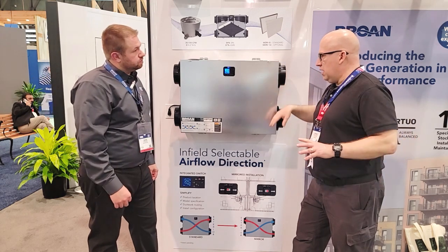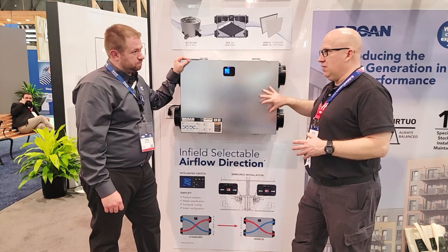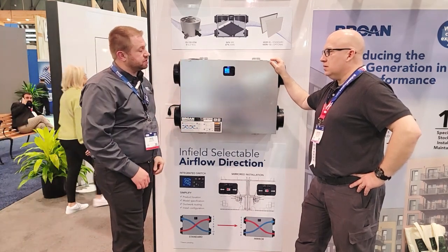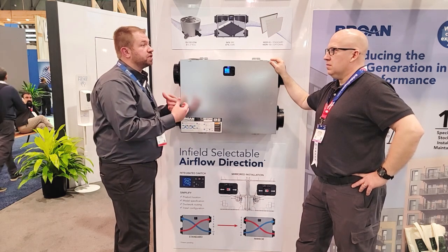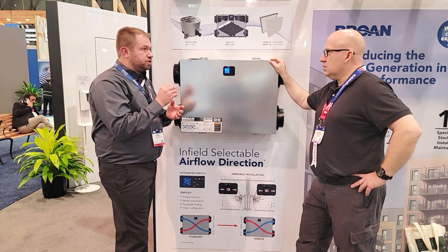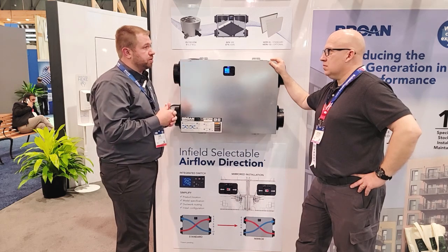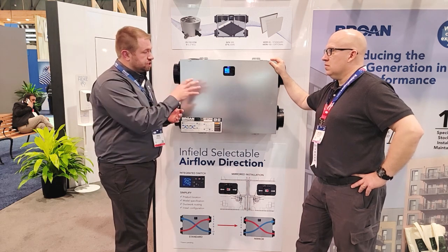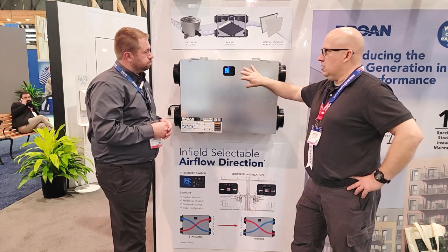This unit features the same Virtuo AI technology as other AI series products. It has an auto-balancing piece during commissioning as well as self-adjusting over time. Once the contractor sets the target CFM, the unit will continue to respond — whether it's filter clogging or exterior termination clogging — and always meet that target CFM that was set initially, within reasonable range.